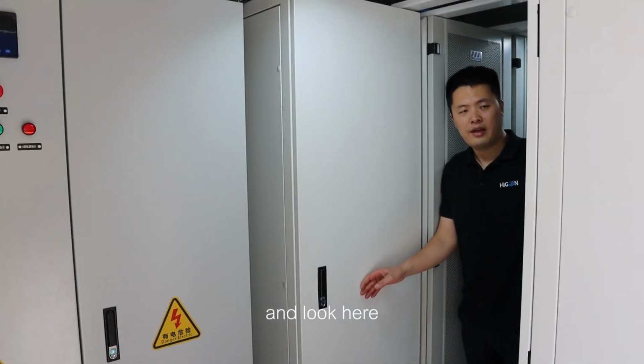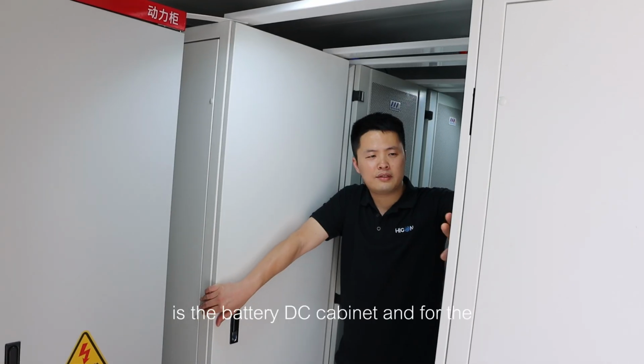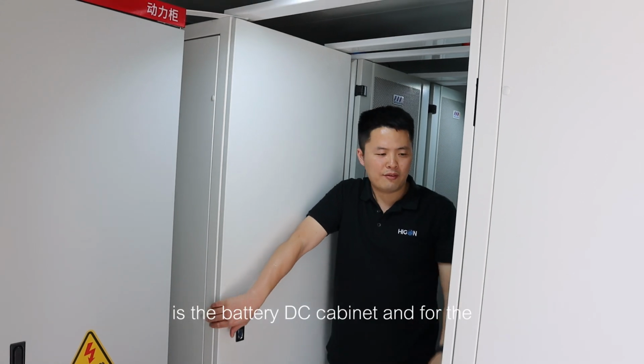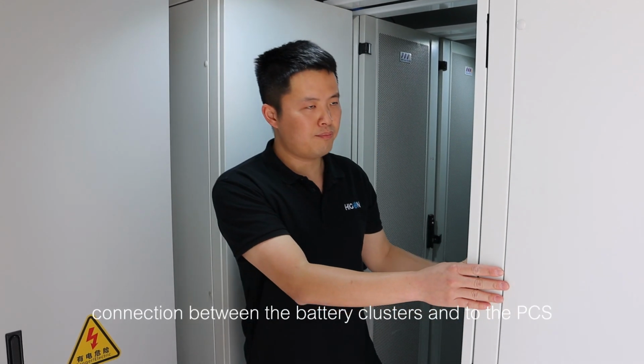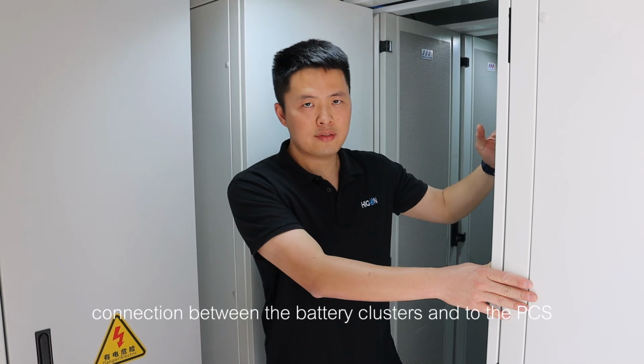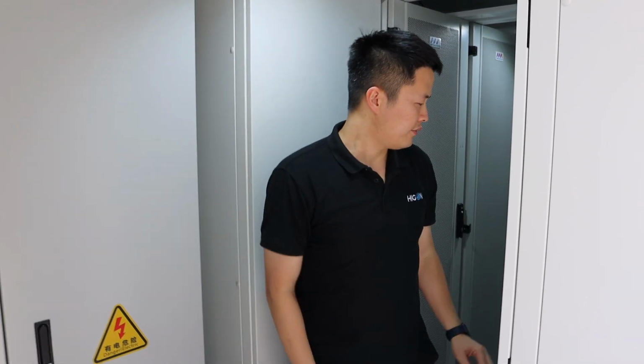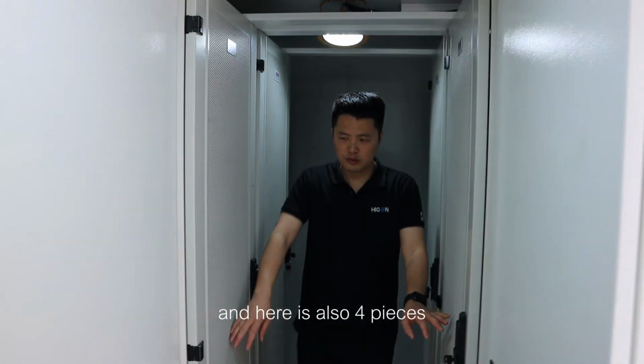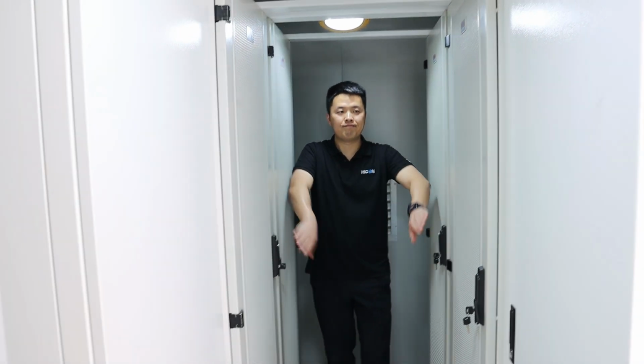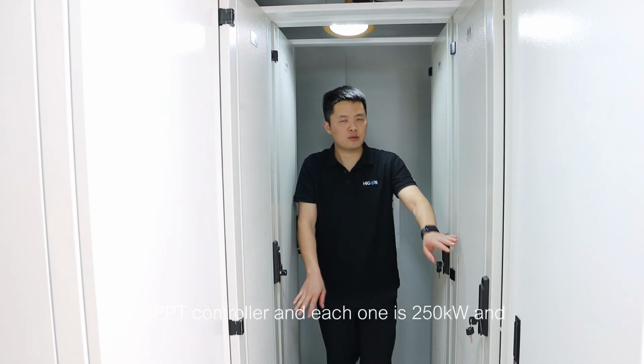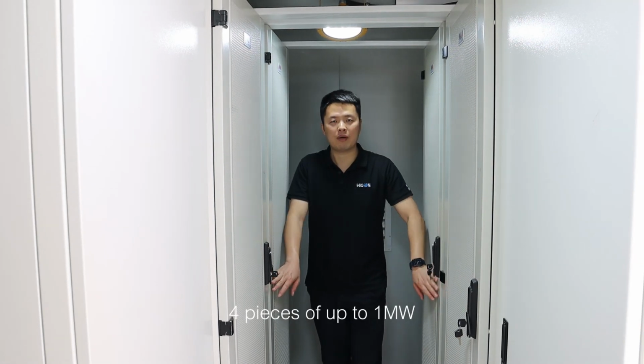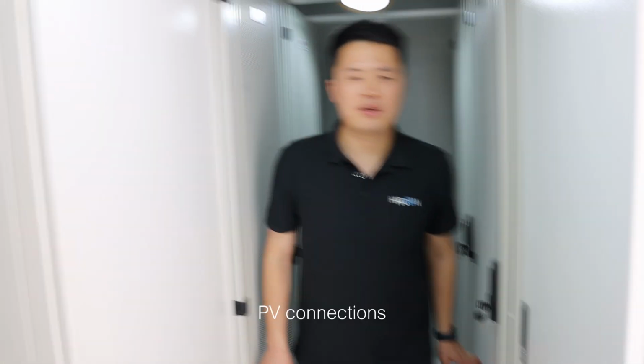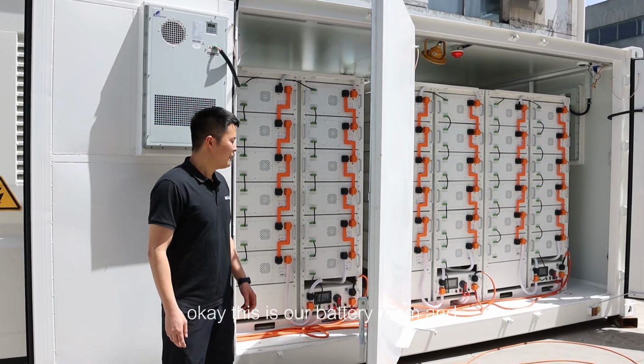And look here, these two are the battery DC cabinets, for the connection between the battery clusters and the PCS. And here are also 4 MPPT controllers, each one 250, so the 4 pieces support up to 1 megawatt of PV connections. Okay, let's see our battery room.